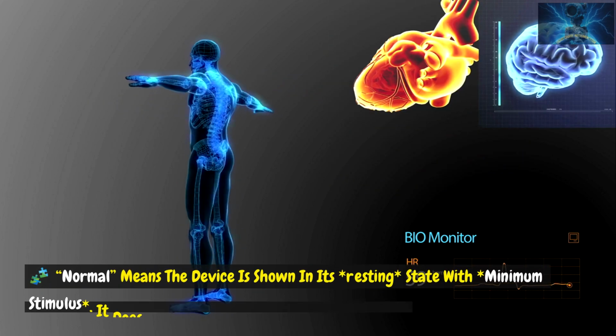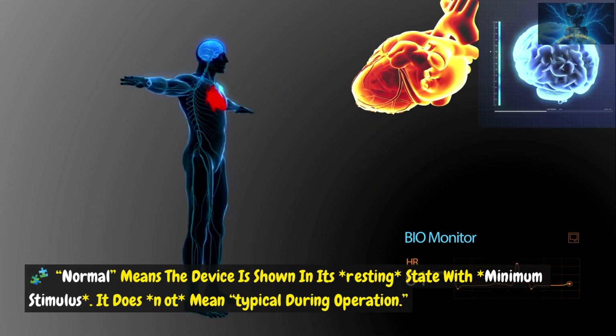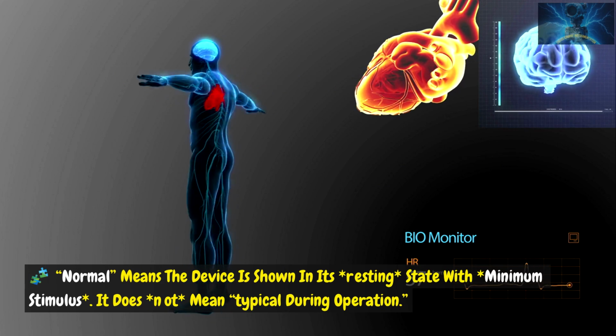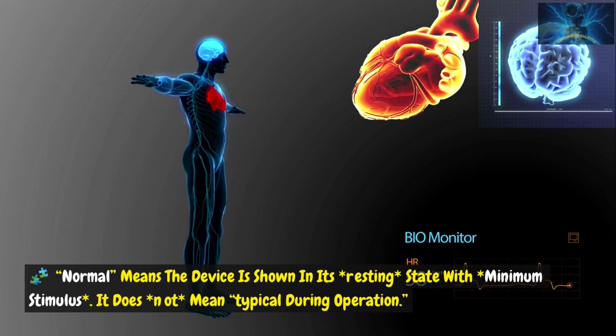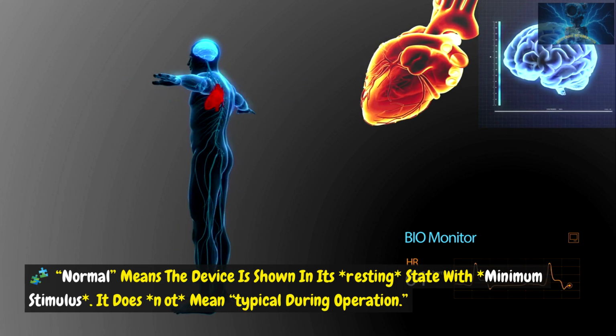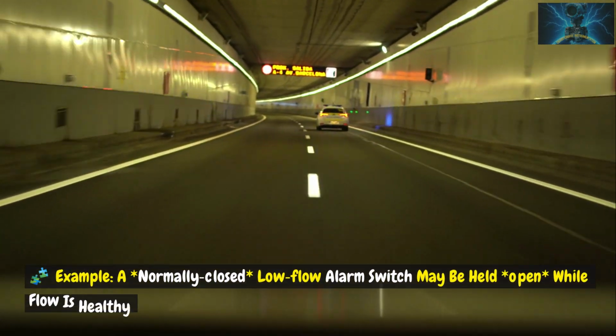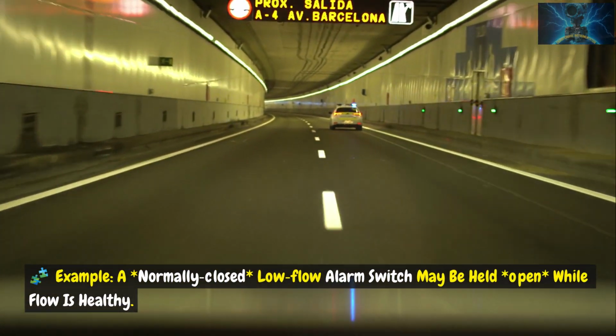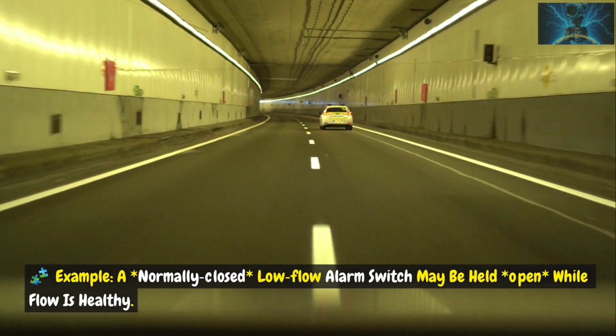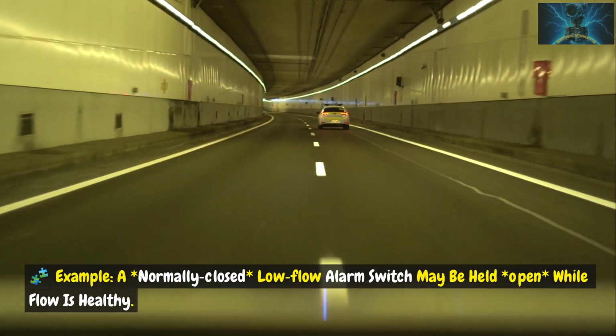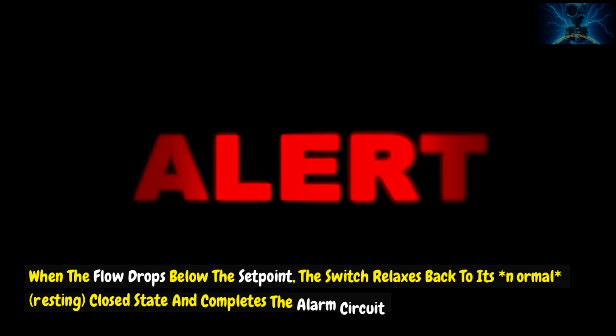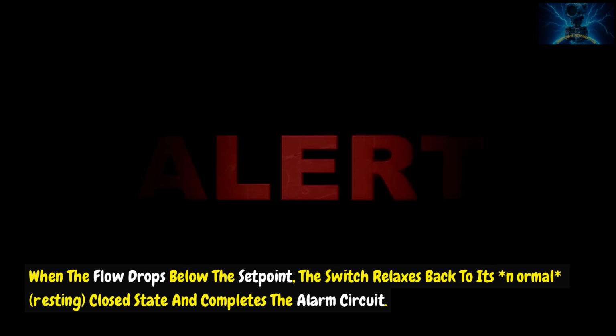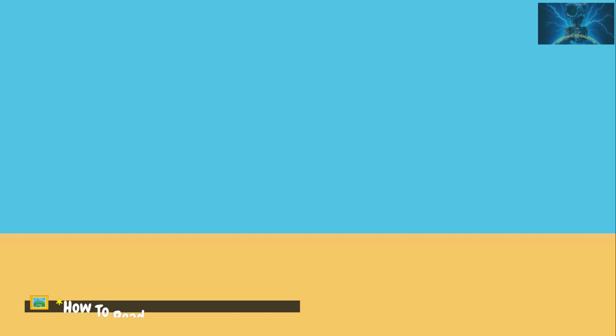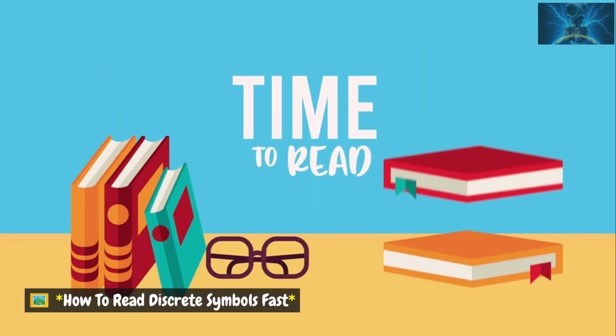Normal means the device is shown in its resting state with minimum stimulus. It does not mean typical during operation. Example: a normally closed low-flow alarm switch may be held open while flow is healthy. When the flow drops below the set point, the switch relaxes back to its normal, resting, closed state and completes the alarm circuit.